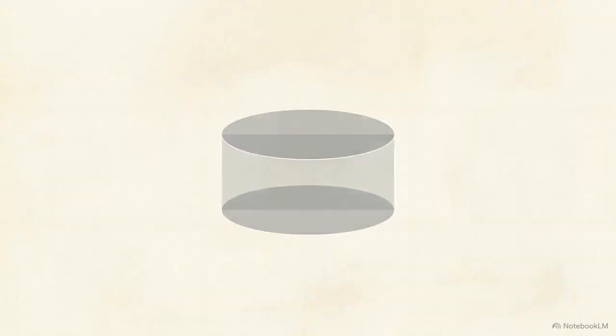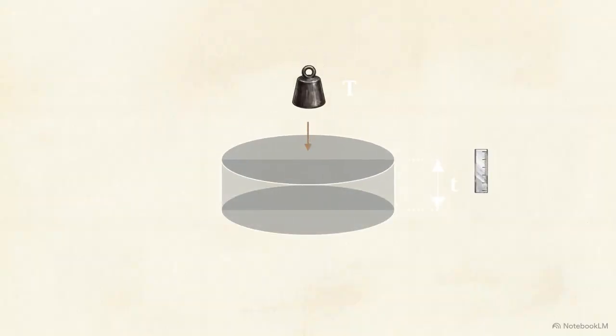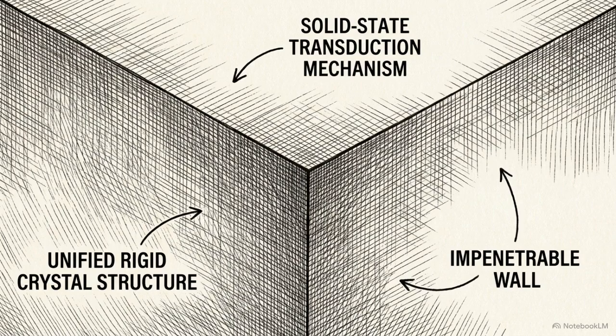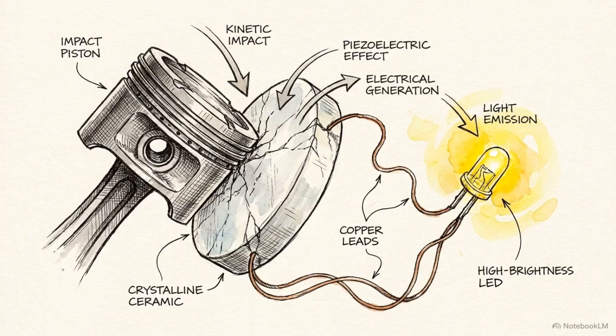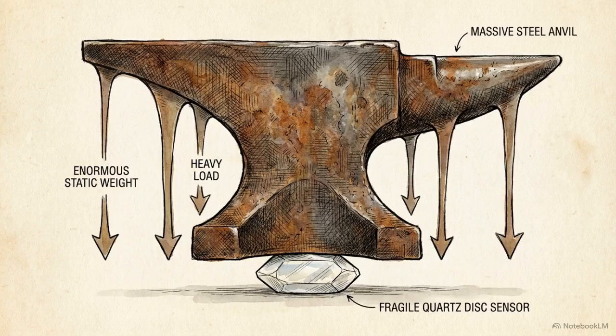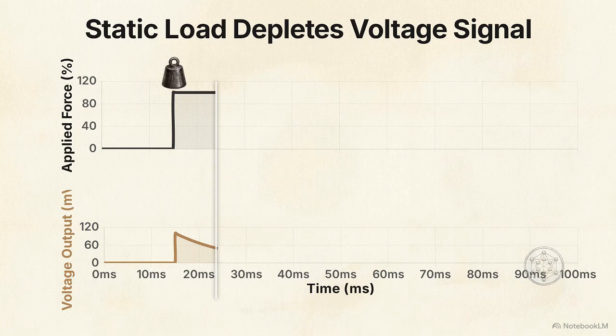That voltage is a function of the material's thickness, the applied stress, and the specific piezoelectric constant of the crystal. There are no moving cores here. The solid material itself acts as the transduction mechanism. These sensors convert kinetic energy directly into electrical potential through molecular deformation. The solid-state design introduces a specific constraint. If a constant, heavy weight is applied to a piezoelectric sensor, the reading will not remain stable. The initial compression generates a sharp voltage spike, indicating the impact of the force.